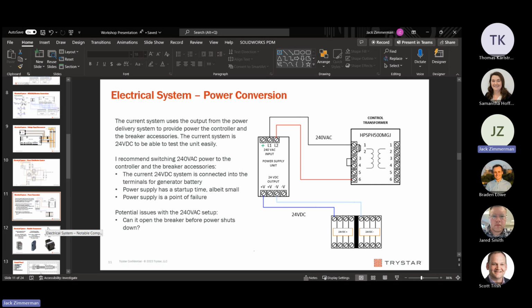And why did we pick the 24 volt? Simply because all of these units need to have, in my opinion, a power test before they go out. With all this wiring, you're able to test the power every bit of the way without bringing it to an energized state that could cause harm. So it's easy. You can just pull up a power supply and test what you're working on right away. It fits our current QC state. Correct. For a future QC state, that's the main reason. Also, 24 volt DC is a nice controls voltage. There are not a lot of other controls devices that use 240 volt AC power, so it's just nice and common.